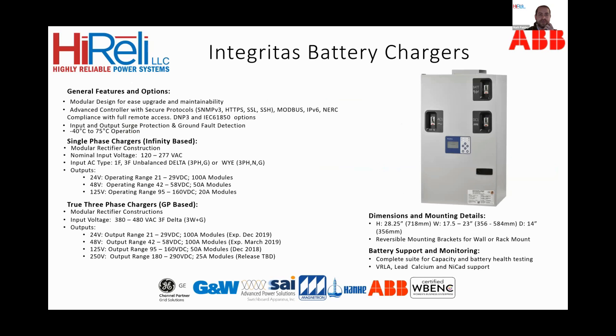Going into more detail with each of these, the Integritas battery chargers offer a modular design with an advanced controller with secure protocols. You can see all the secure protocols that they offer. The input ranges for this are from 120 volt AC to 277 volt AC single phase, and 380 to 480 volt AC three phase. Depending on your needs, the outputs can range from 24 volts DC up to 125 volts DC at different current ratings. And you can see on the right, the physical footprint of these is pretty small. It's a 28-inch high cabinet by 23 inches wide and 14 inches deep. So if you have a tight application in your control house, this would be a great fit for it.